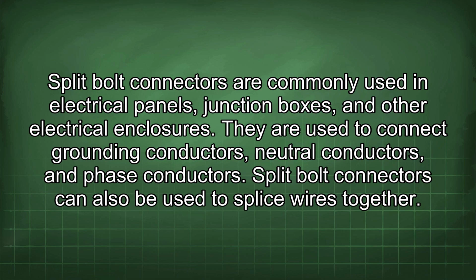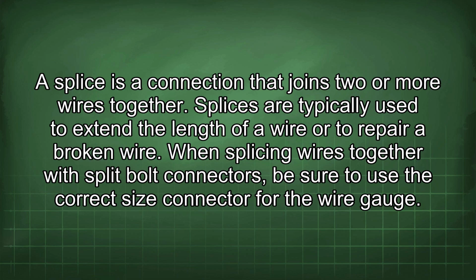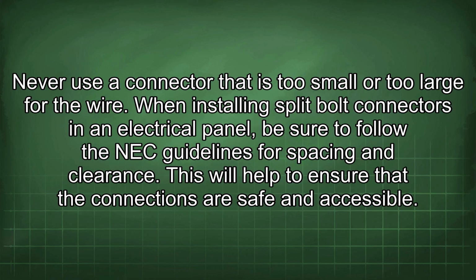Split bolt connectors can also be used to splice wires together. A splice is a connection that joins two or more wires together. Splices are typically used to extend the length of a wire or to repair a broken wire. When splicing wires together with split bolt connectors, be sure to use the correct size connector for the wire gauge. Never use a connector that is too small or too large for the wire.